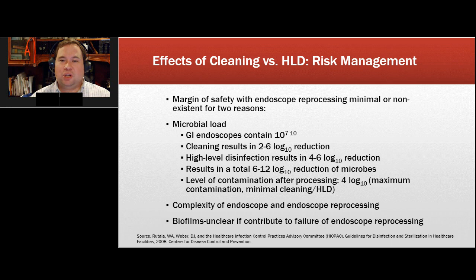One final example is that we're not just seeing this in the perioperative space, but we're seeing challenges with other reusable devices that have high frequency of use in healthcare, like ultrasound probes. In this particular example, as it relates to the placement of things like PICC lines and other vascular access devices, we know that we have practice-related issues, but also we have challenges with how devices can be reprocessed. If I'm going to use a device, for example, that's going to come in contact with, let's just say, non-intact skin and mucous membrane, then by definition, that device should be high-level disinfected. If it's going to come in contact with sterile body cavities, then we know that we have to sterilize that device. And so there's a lot of challenges with uniformly handling these types of devices that might be used.